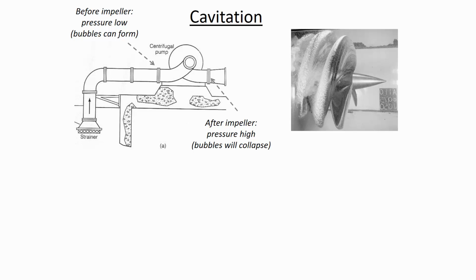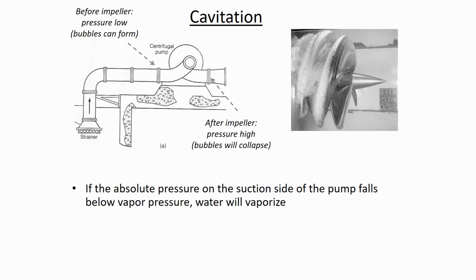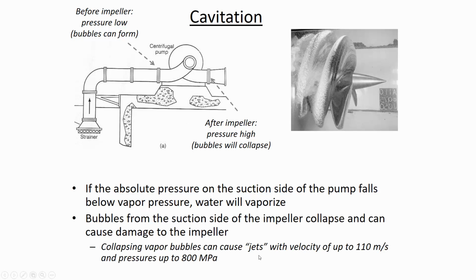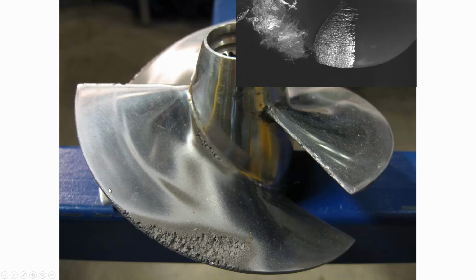Now, cavitation is the problem that can occur when you've got low pressure, and getting lower in the direction of flow. So here is a picture of some tiny little vapor bubbles that are forming as the water is encountering the impeller. Because on the impeller surface itself, there's a high pressure side and a low pressure side. And those tiny little water vapor bubbles, when they collapse, when they get to the high pressure side, they can cause jets with a velocity of 110 meters per second and pressures up to 800 megapascals. And so they're small little vapor bubbles, but they have a lot of energy in them. And over the long term, those little cavitation bubbles can erode the surface of the impeller and cause a lot of physical damage to the pump.